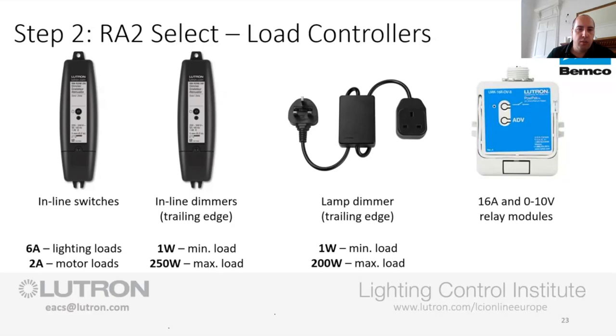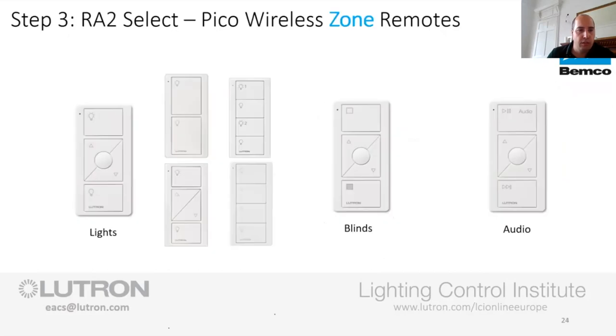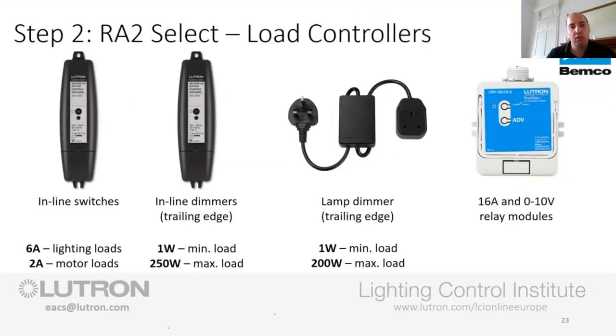Now, the one thing, if you look at the Aurora one that I showed you earlier, that was 62 lamps, 5 watts a piece. Do quick maths, that comes over 250 watts. Okay, so if it's on our test report and we say you can do that, you can do that. But this is just a rough rule of thumb that you're not going over the 250 watts of load.